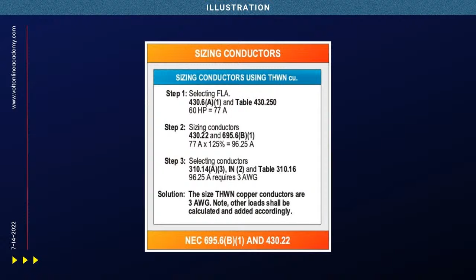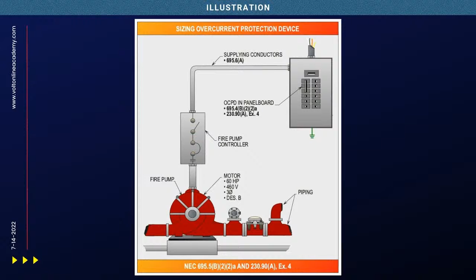Now, the next thing I'm going to be looking at is the overcurrent protection device in the panel board. And you're going to see here, it's going to reference 695.4(B)(2)(a) and 230.90(A), Ex. 4, which is going to refer you and tie this in when I'm dealing with fire pumps. Now, when I get over here and look at this, it's going to tell you that you still use the 77 amps for the overcurrent protection device.